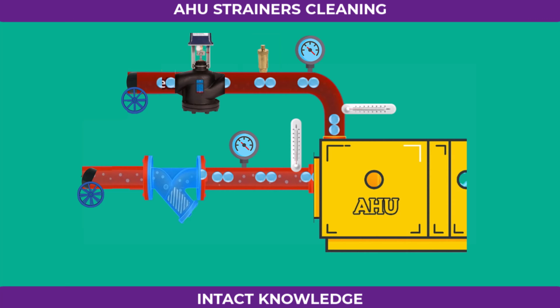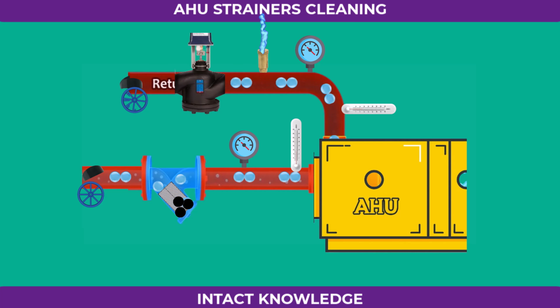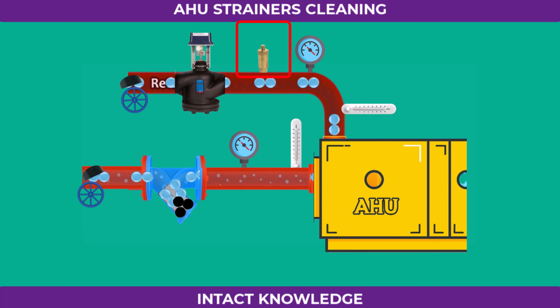Then, gently open the supply line valve so that water slowly begins to fill the pipeline. As the water flows in, it pushes the trapped air through the line toward the return side. When the air reaches the air vent, it will start escaping from there. At first, a mix of air and water will come out, but once the air is completely released, you'll notice only water flowing from the vent. Once that happens, close the air vent.